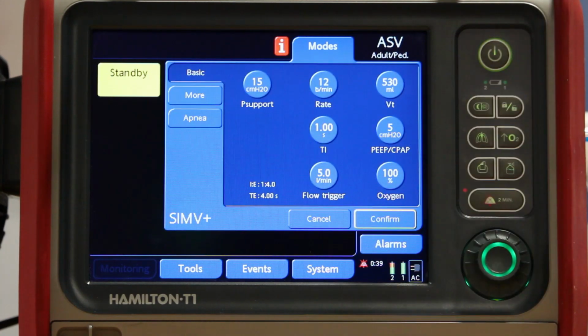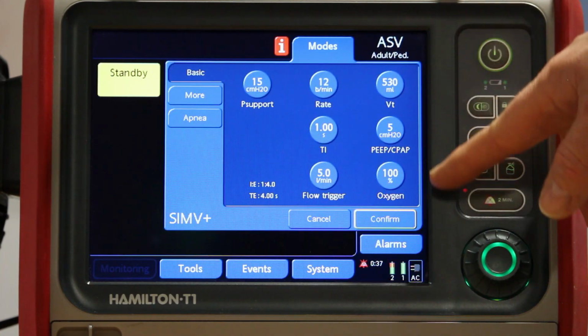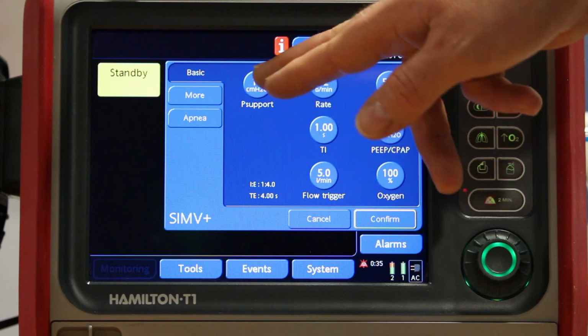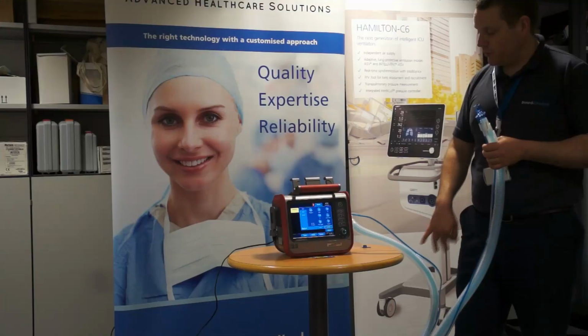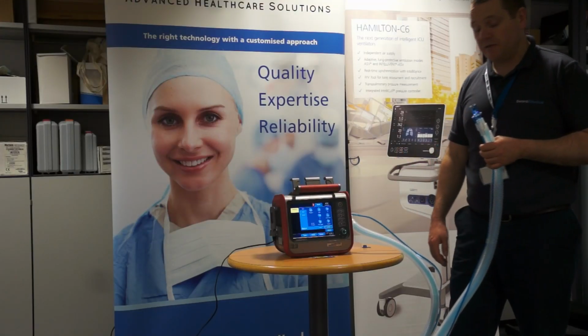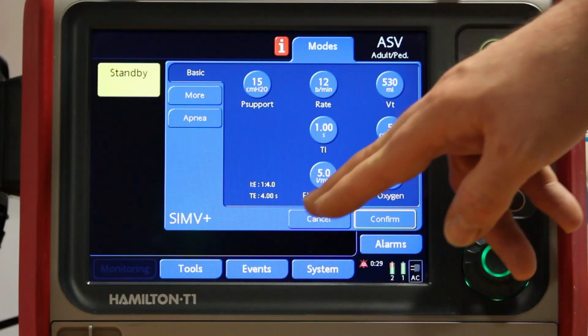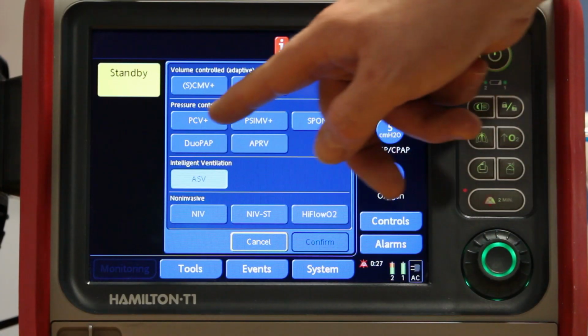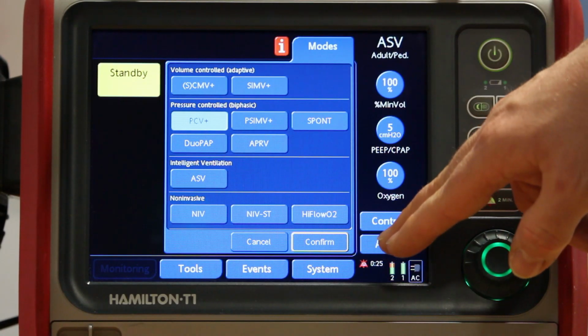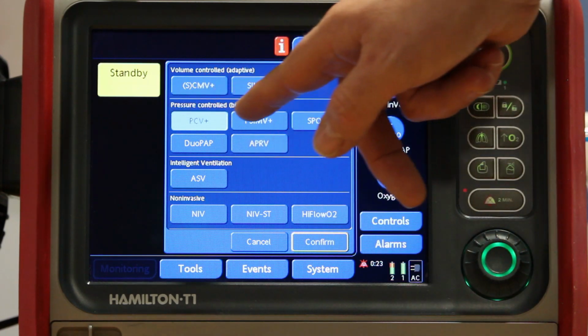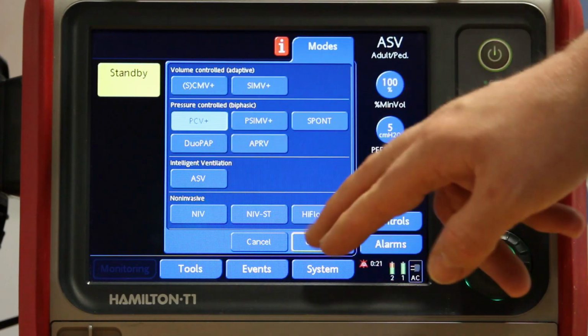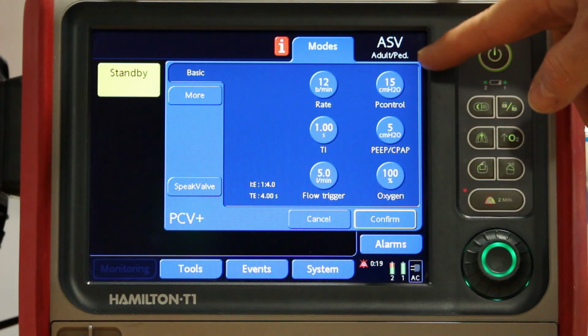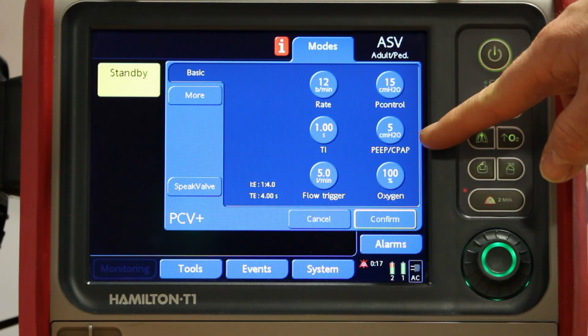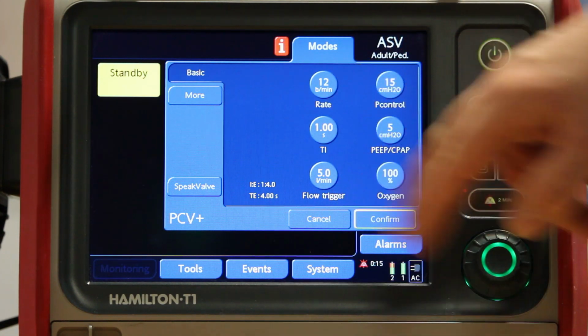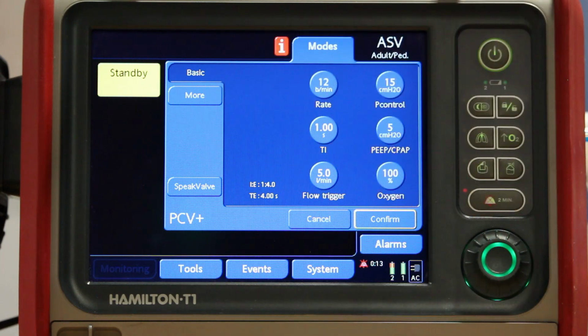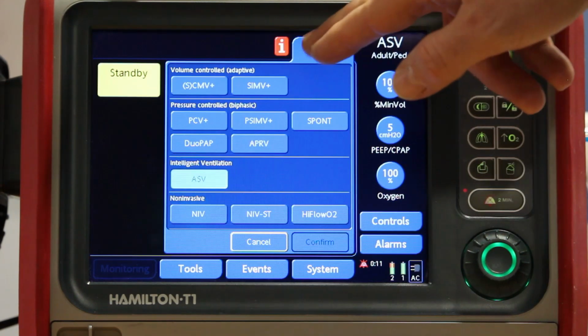SIMV, synchronized intermittent mandatory ventilation. So there's all the same settings as CMV, but we do have pressure support for any breaths that the patient triggers themselves, so the ventilator will synchronize with patient activity. PCV is pressure control ventilation, and these are labelled pressure controlled, these 5 modes underneath. And PCV is pressure control, so we're setting our inspiration pressure and our PEEP. We've got a rate, an I time and a trigger. Again, there's no support in the mode for any patient triggered breaths.